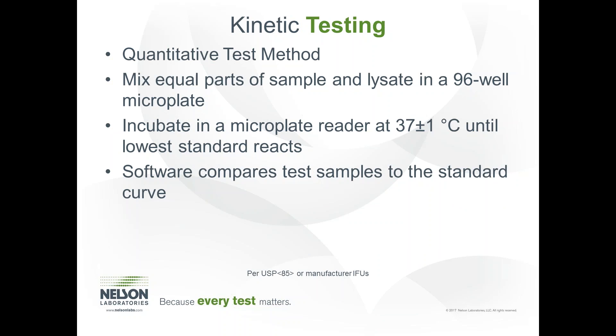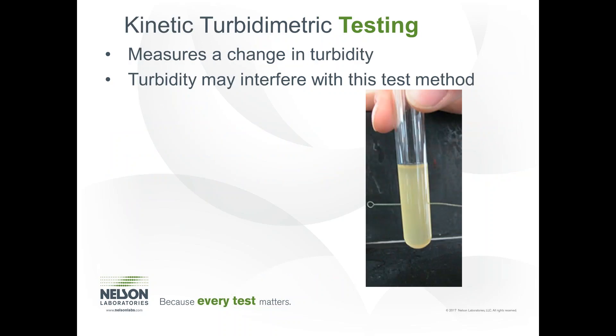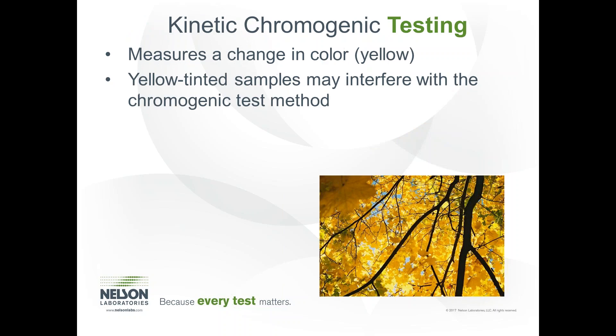Kinetic testing is a quantitative test method. You mix equal parts of sample and lysate in a 96-well microplate, and it is read with an incubating photospectrometer. The test runs until the lowest standard reacts, and the software then compares the unknown reaction times of the sample to the known reaction times and endotoxin concentrations of the standard curve. Kinetic turbidimetric testing measures a change in turbidity — samples go from clear to a milky white color as the reaction takes place. Samples that are inherently turbid can interfere with this method. The chromogenic test method uses a chemically modified lysate that changes from clear to yellow instead of clear to turbid, but yellow-tinted samples may interfere with the chromogenic test method.